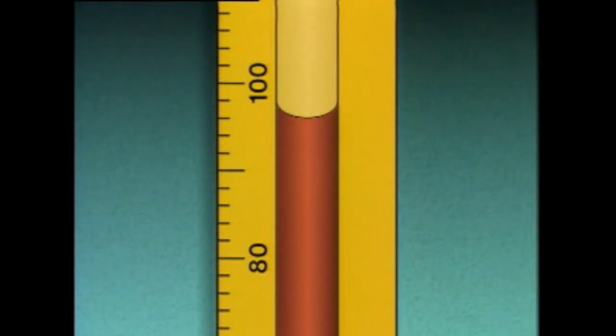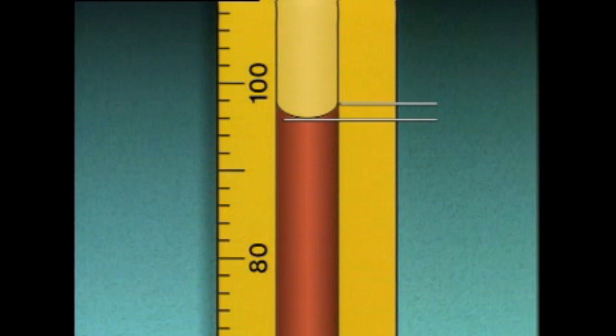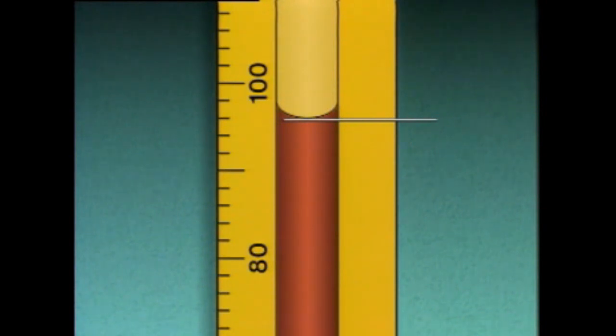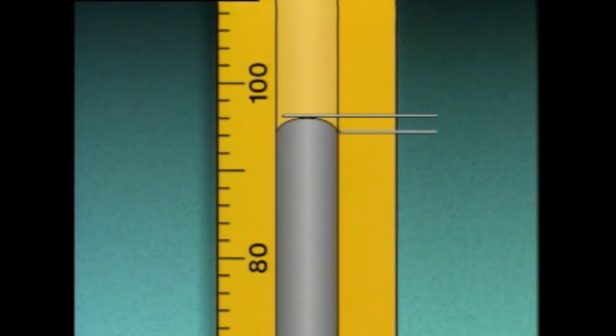The free surface of a column of liquid forms what is known as a meniscus. Water and oil both form a concave meniscus, which means that the center of the column is lower than the outer edges. The level of any meniscus should be read at its center, so the level of a concave meniscus is read at the lowest point. Mercury, on the other hand, forms a convex meniscus, which means that the center of the column is higher than the outer edges. So the level of a convex meniscus is read at the highest point.